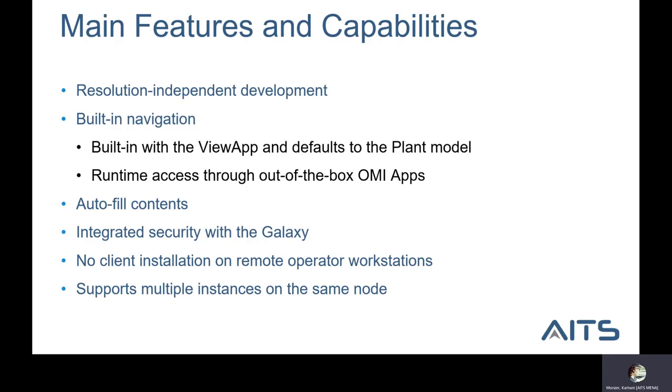As well, there is no client installation on the remote operator workstations. That means I don't have to install anything, just the basic bootstrap part. Unlike InTouch for System Platform, where for the operator I have to install InTouch Application Manager and WindowViewer, and for the engineering station I have to install WindowMaker plus WindowViewer plus InTouch Application Manager.